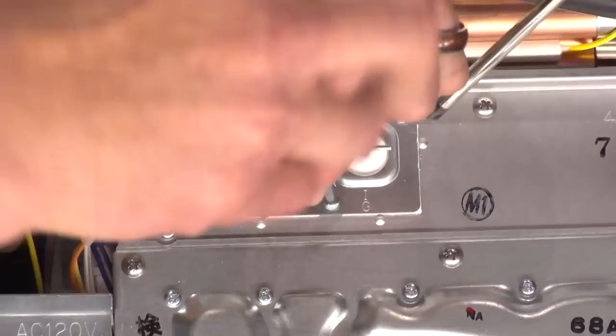Now it's held in by 3 screws. You just go ahead and take these smaller screws out. These are going to be a little different than the other screws we'll take out today. Remember these 3 screws go with the flame sensor igniter—you'll understand once we start pulling this apart. These are the only 3 small screws like this we're going to take loose.